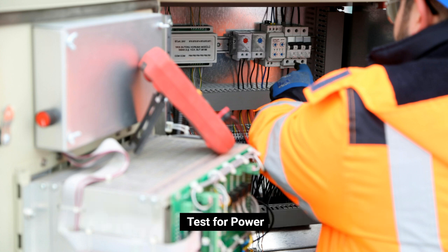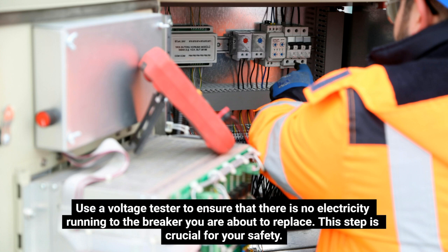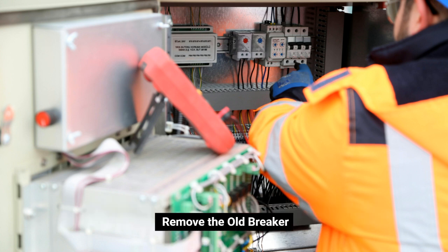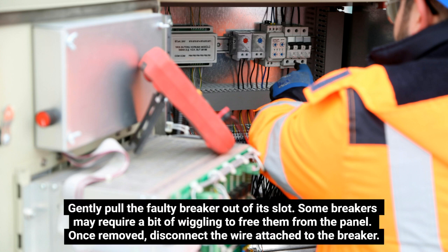Test for power. Use a voltage tester to ensure that there is no electricity running to the breaker you are about to replace. This step is crucial for your safety. Remove the old breaker. Gently pull the faulty breaker out of its slot. Some breakers may require a bit of wiggling to free them from the panel. Once removed, disconnect the wire attached to the breaker.